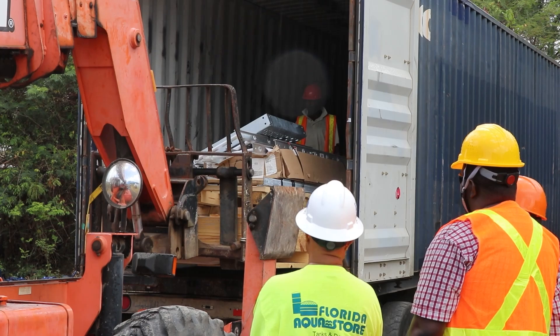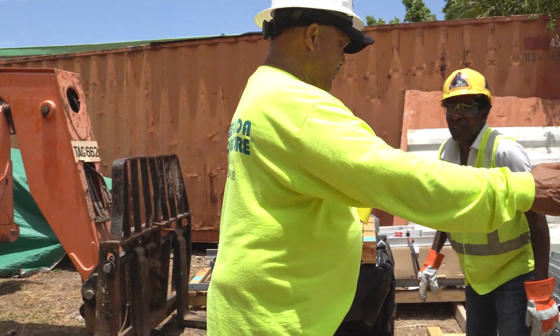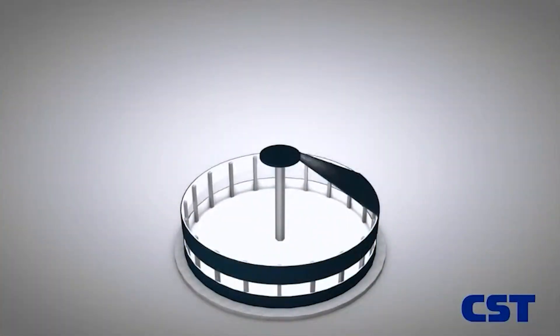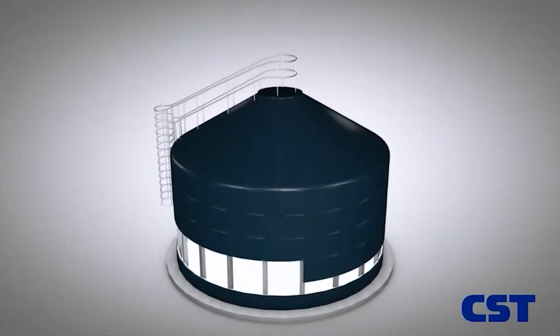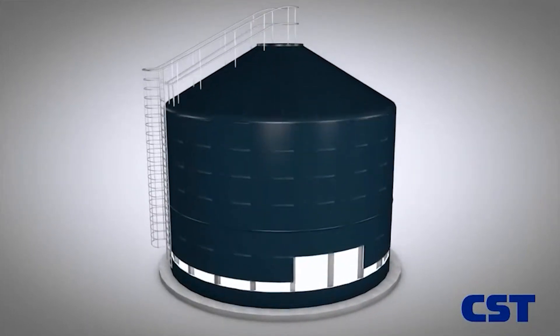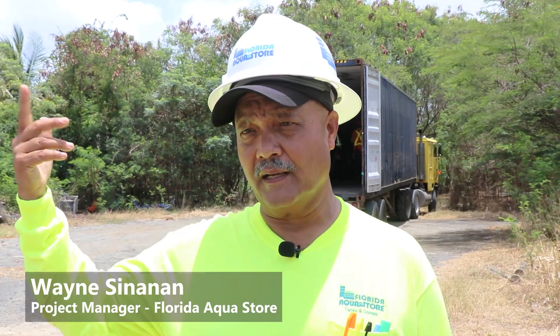Tank construction will be undertaken by Florida Aqua Store. Representative Wayne Sinanan provides insight into the construction process, highlighting the meticulous attention to detail and safety measures employed to ensure the durability of the tanks. After the foundation is done, the tank is built from the top down. This is possible with our specialized jacking equipment. This way, we build the first ring, we build the dome, then we jack up the tank, and we put in the other rings. After each ring, we jack it up and put on the next ring. All our work is at ground level at that point in time. This is a very safe construction method, eliminating the need of having workers work at heights, on scaffoldings, and all that.